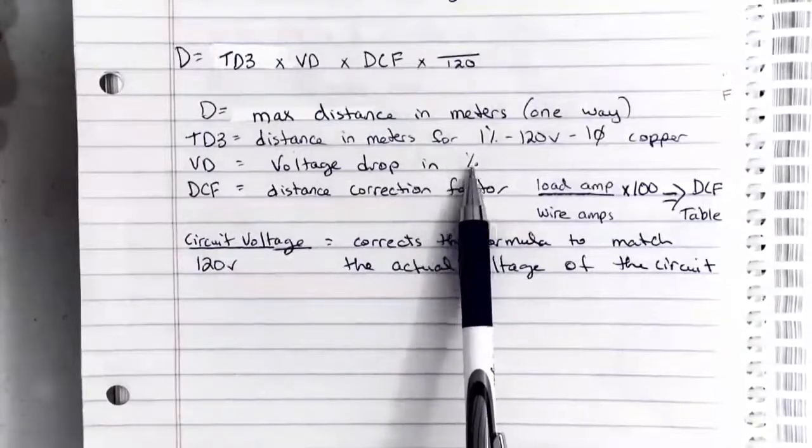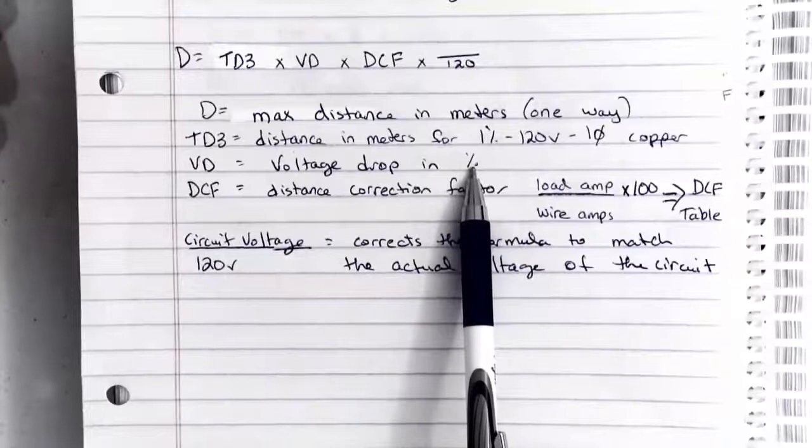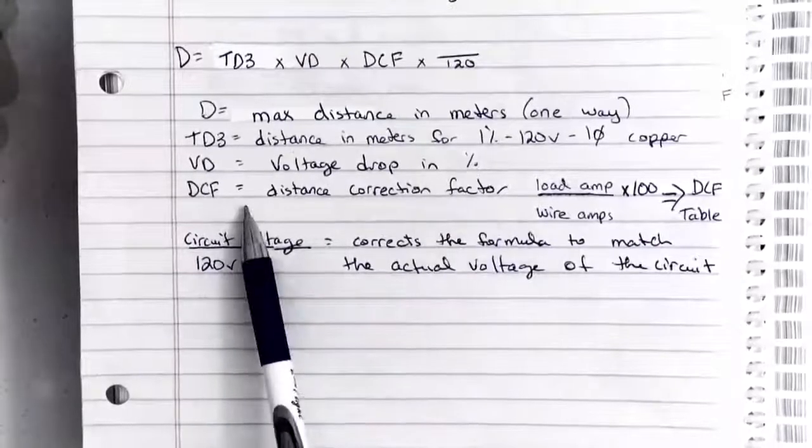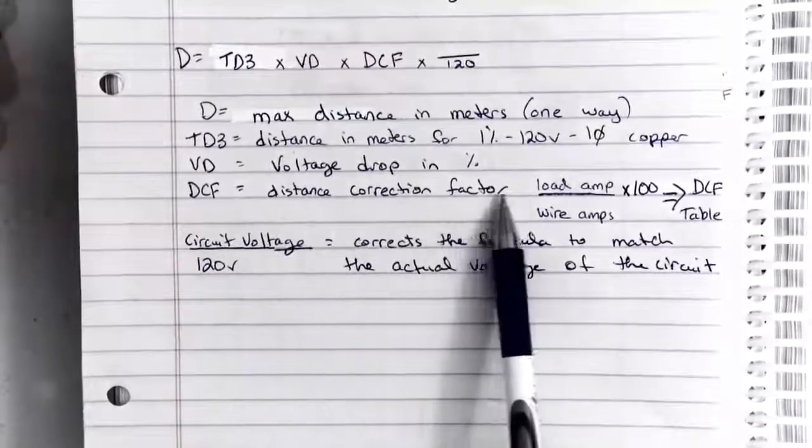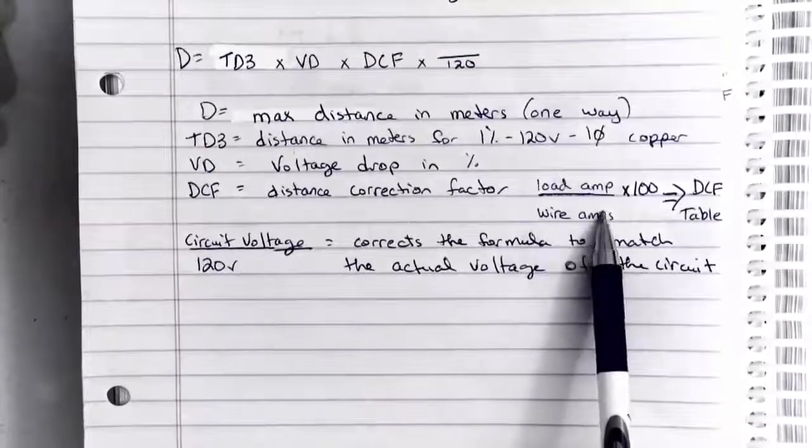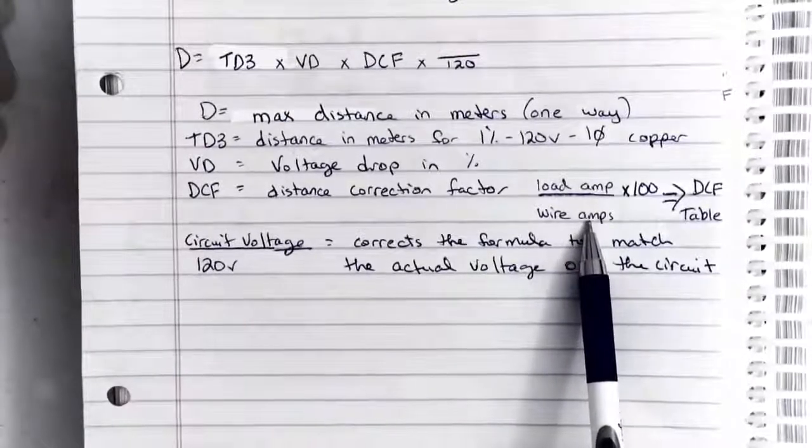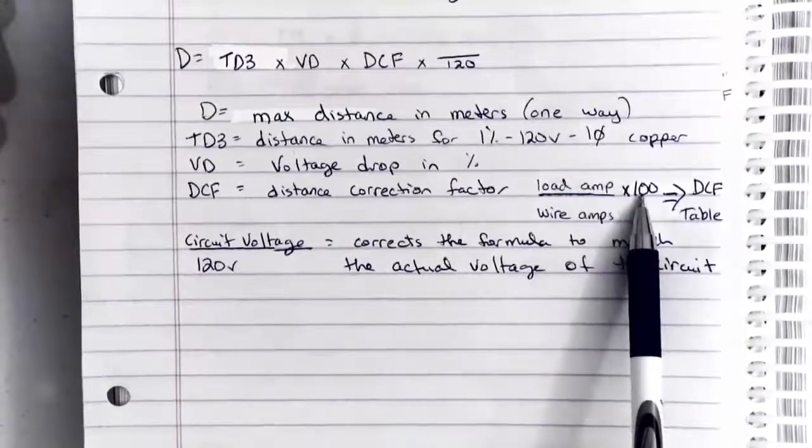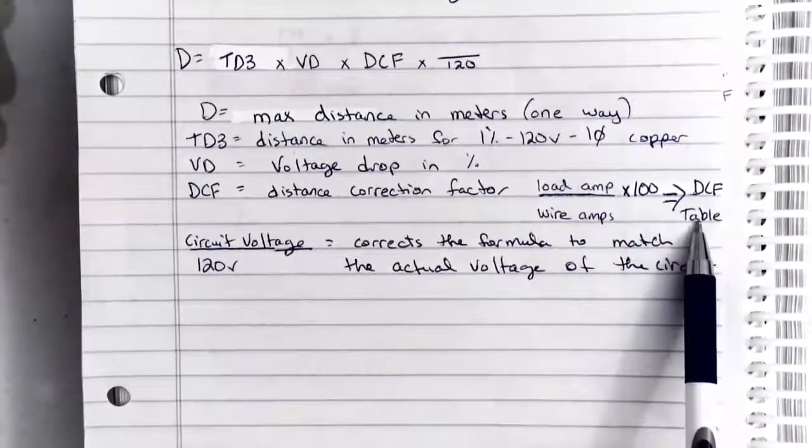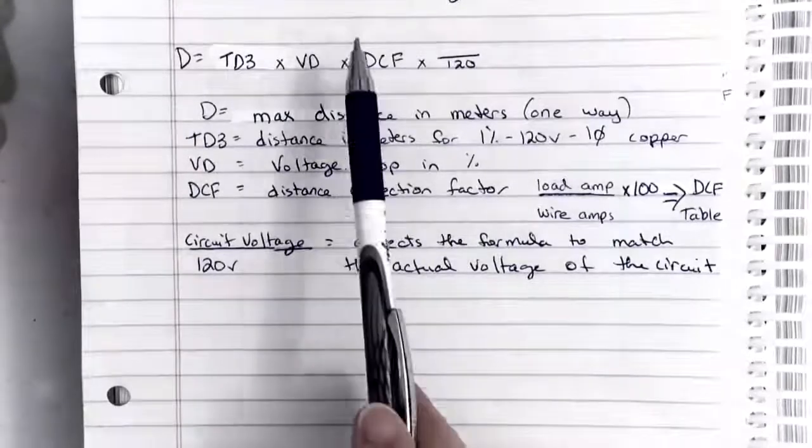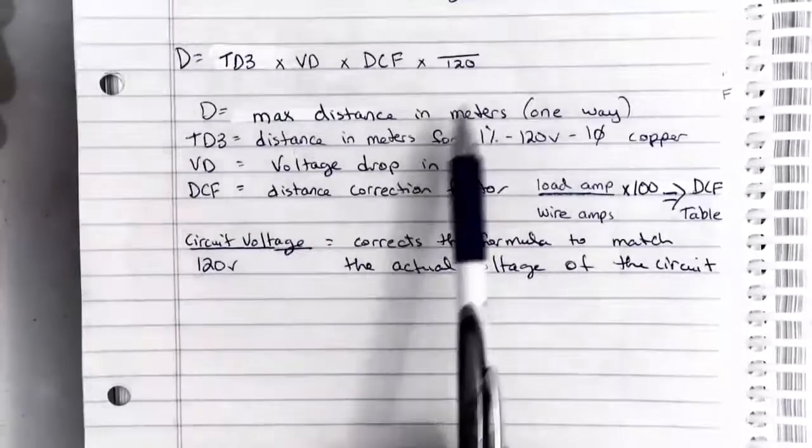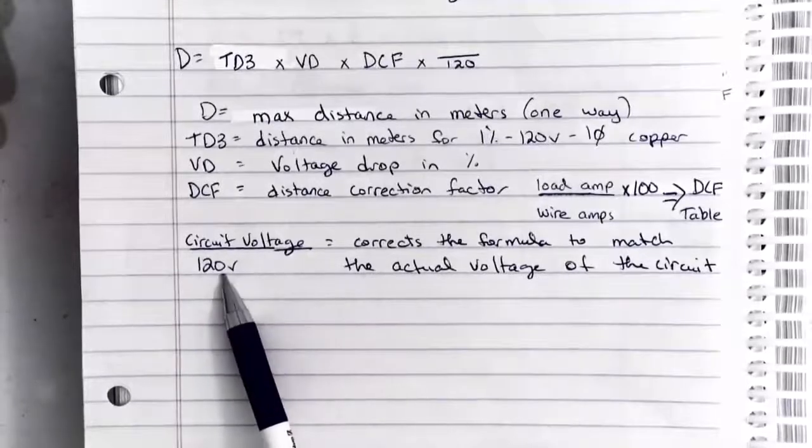The voltage drop is in percent, so we don't change that to a decimal value. We leave that in percent. So if it's 3%, we just put the number 3 in this calculation, not decimal 0.03. And the distance correction factor is found this way: we take the load amperage divided by the capability of the wire that we're using, so the wire amperage, multiply that by 100 and we get a percentage. We're going to then take that percentage to the DCF table and look up the value that we would put in our formula up here for DCF. And the last piece was the circuit voltage, the actual circuit voltage divided by 120.